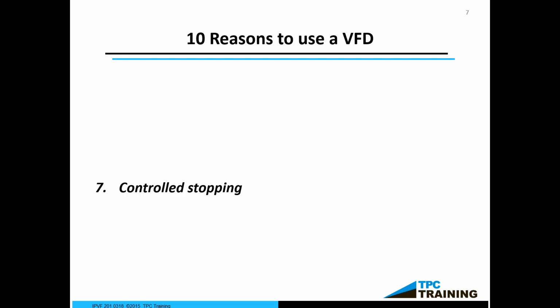Controlled stopping. Maybe you need a dynamic brake. Maybe you want to coast to a stop. When we program these drives, whether by the keypad or by the computer, we get the information either from our own design people or from the engineers to set it up. This is going to be part of a total system. The drive itself is part of a total system. It's not the conveyor, but it does drive the conveyor.